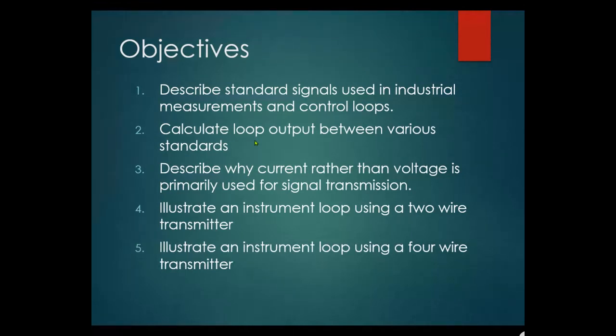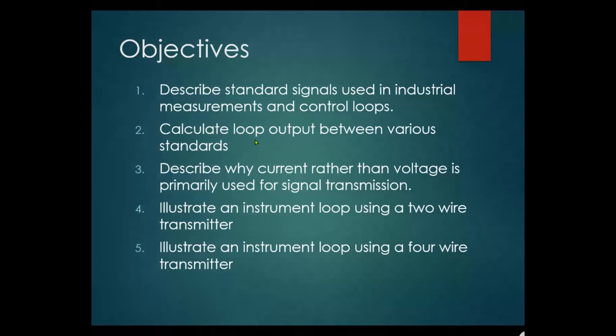Illustrate an instrument loop using a four-wire transmitter. In a four-wire transmitter, two wires are power wires and the other two are loop wires. This is used when the loop requires a lot of power — for example, a mag meter requires a lot of power, so it uses a four-wire system where two wires are just power wires.